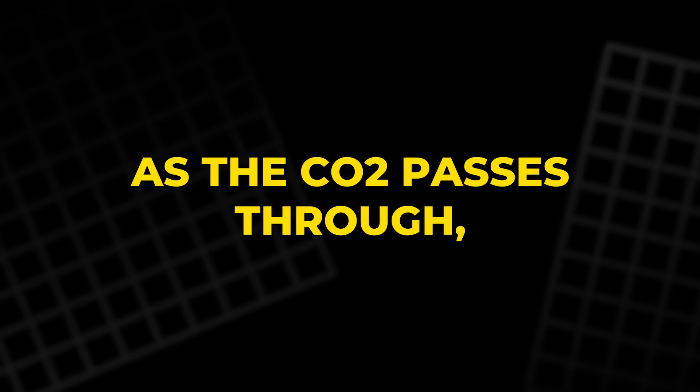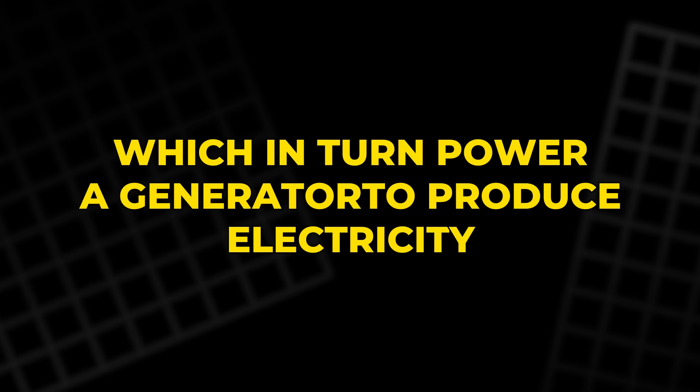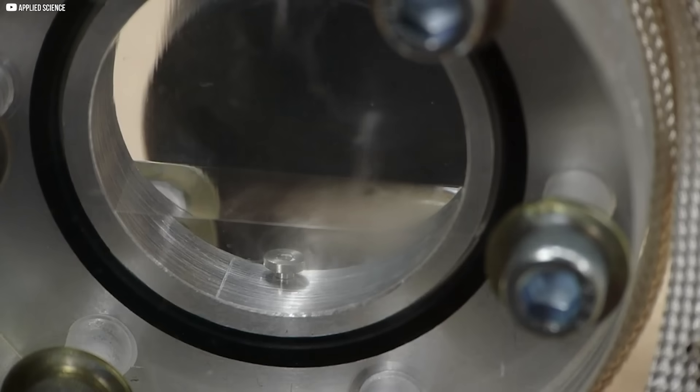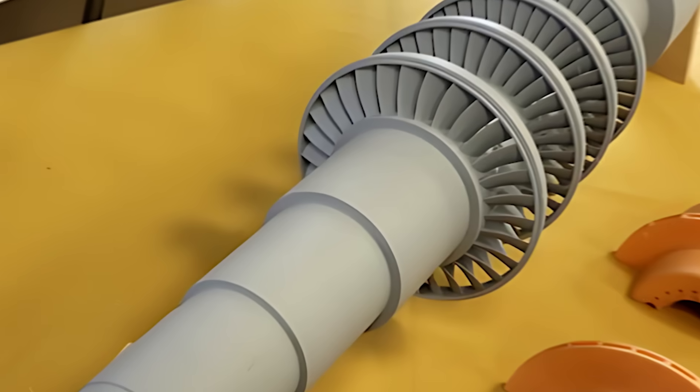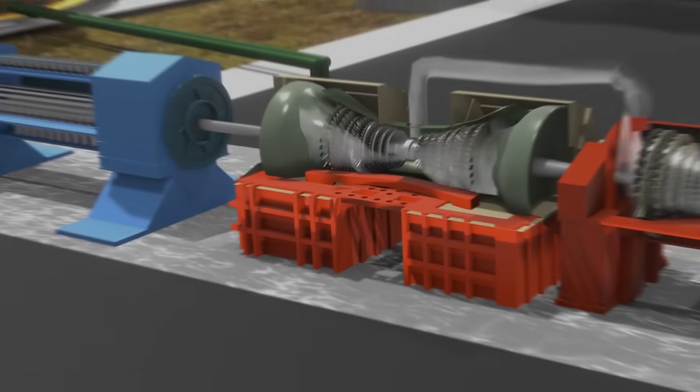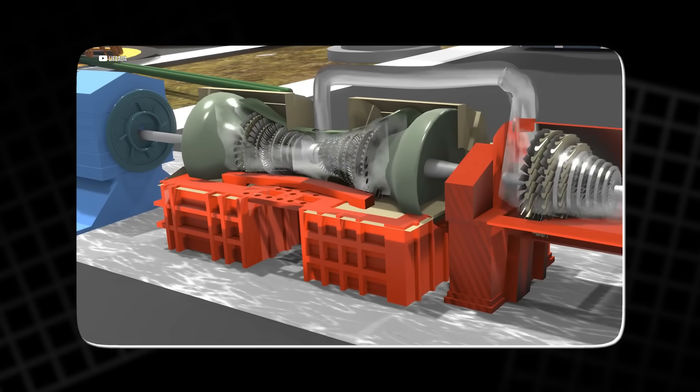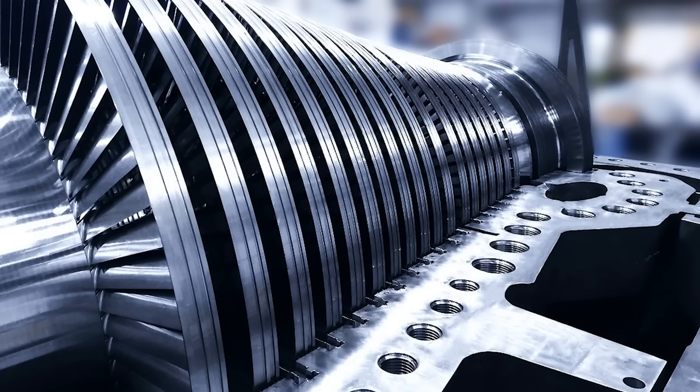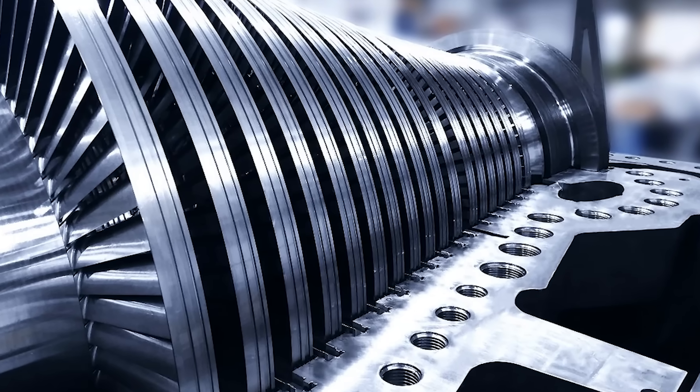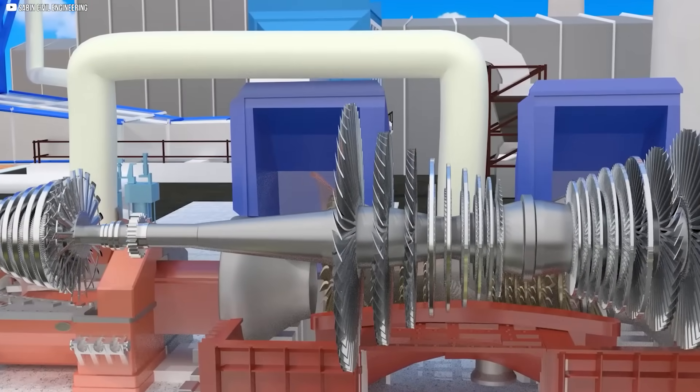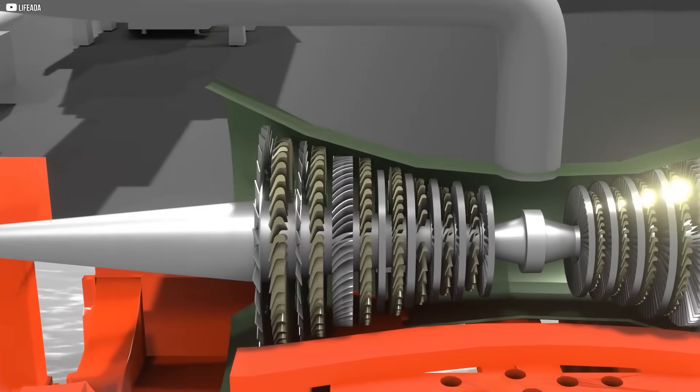As the CO2 passes through, it spins the blades, which in turn power a generator to produce electricity. The key difference here is that supercritical CO2 is much denser than steam, which means turbines can be significantly smaller and more compact. A supercritical CO2 turbine can be up to 10 times smaller than a comparable steam turbine, making it ideal for applications where space is limited. The high density also allows these turbines to generate more power for their size, increasing overall efficiency.